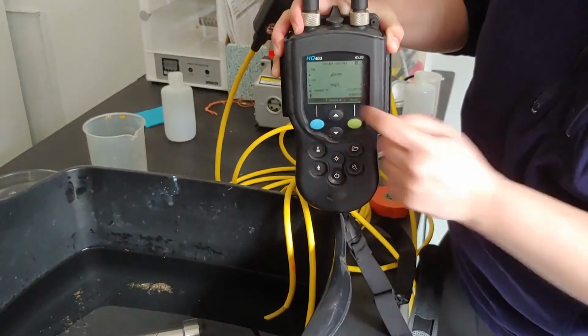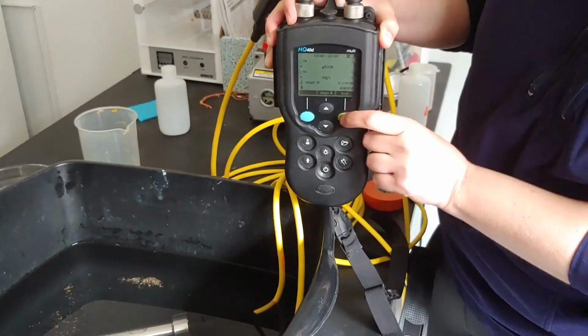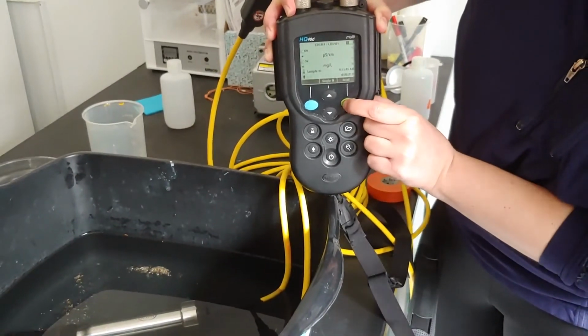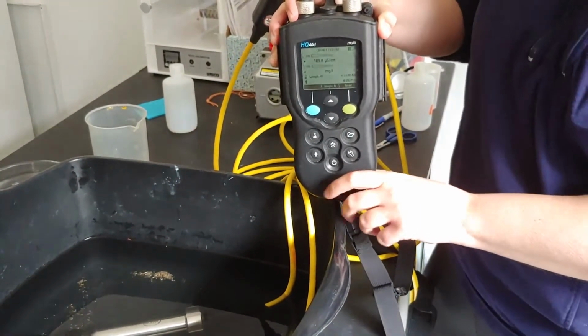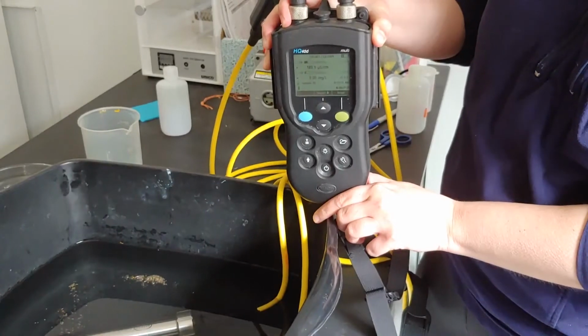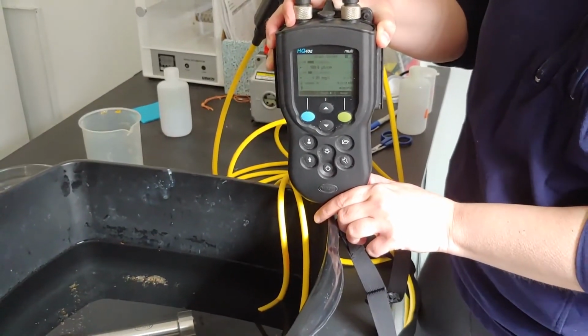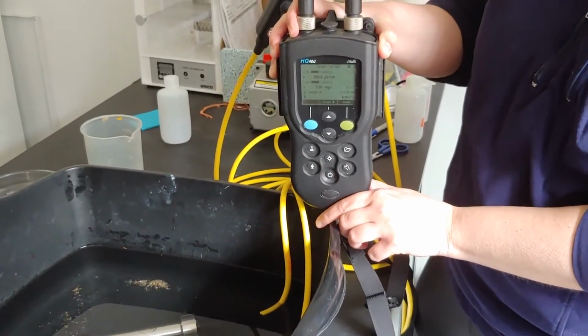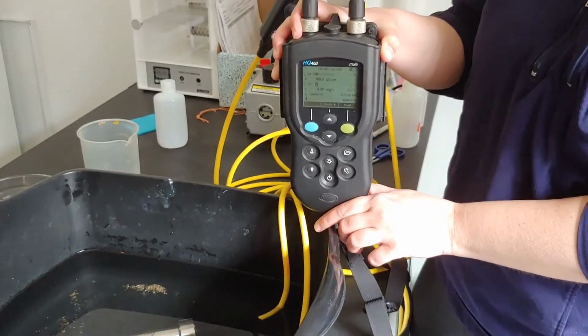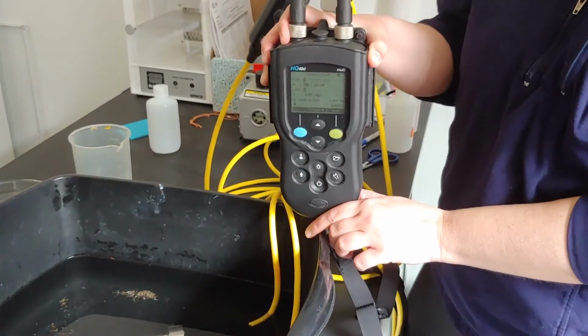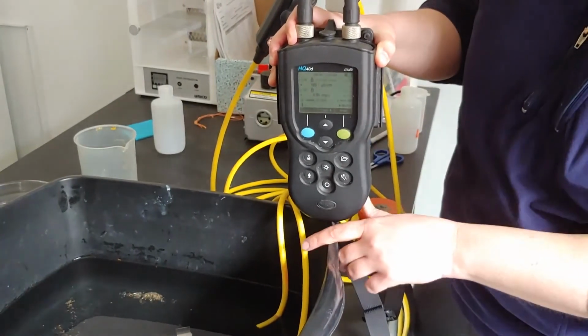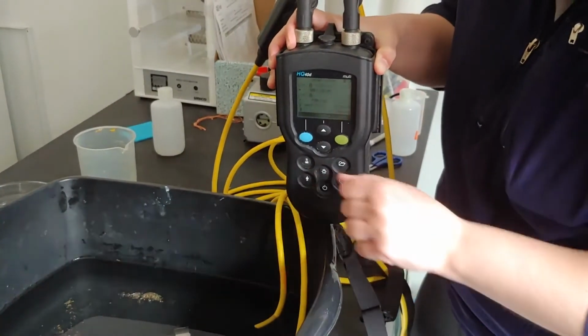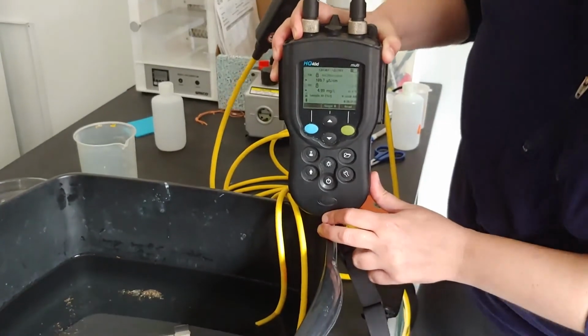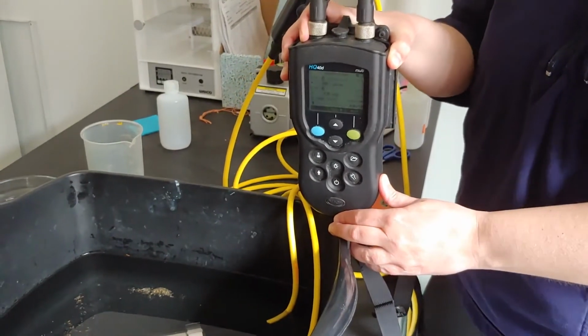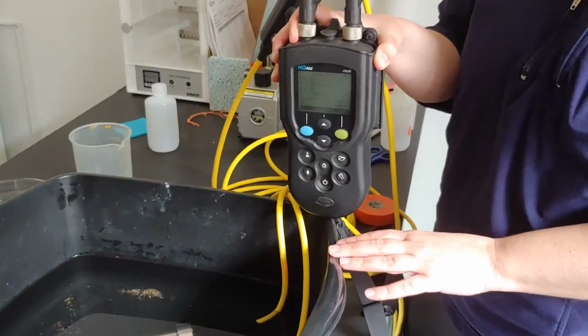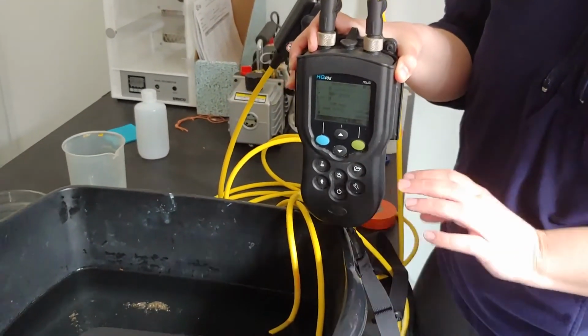Once I have confirmed that I see those two OK symbols, I am now going to hit the green read button. Now I should see a status bar come up for both probes, and you may find that one probe takes a little bit longer than the other, and that's okay. Sometimes dissolved oxygen will click into place really fast and conductivity may take a while. Other times the opposite is true. Now, what you can actually see from the probes themselves is as the DO probe is functioning, you will see a red and blue light flashing on the actual probe itself. This is normal and expected, so it's nothing to worry about.